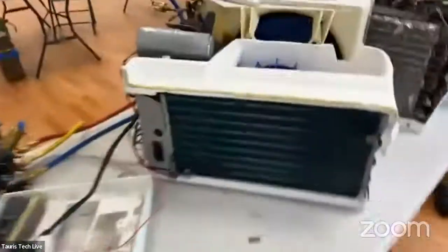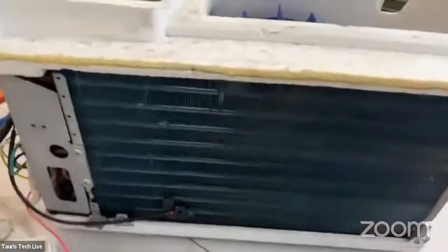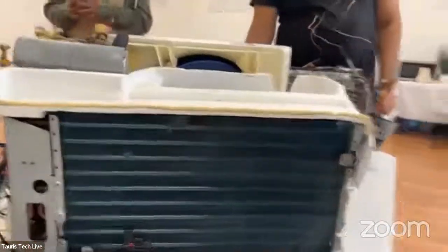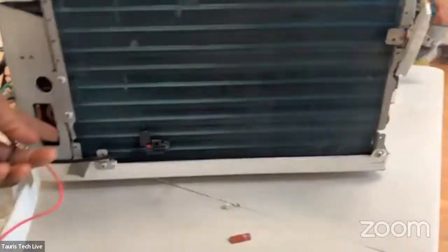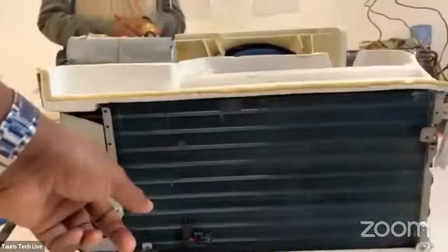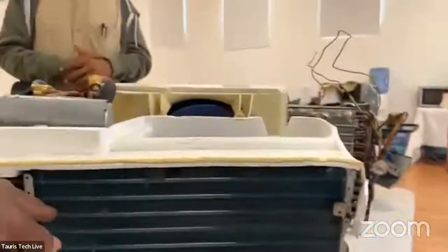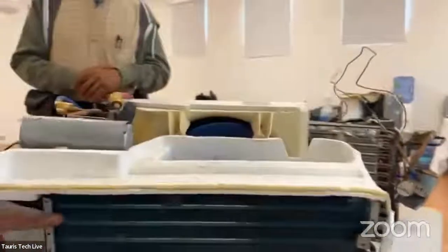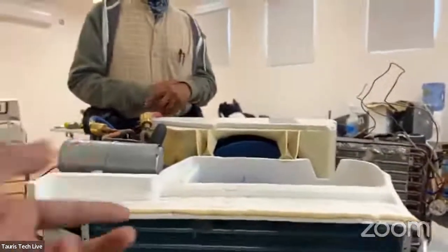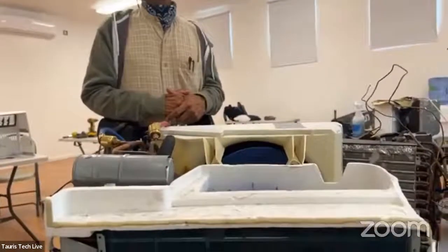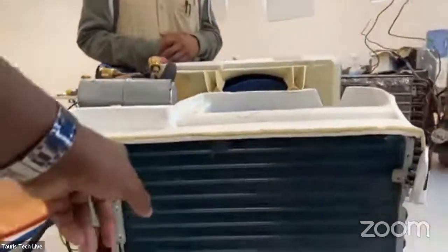Okay. So we have our evaporator coil here, right? If you imagine that our liquid refrigerant is entering down here and it's boiling as we go through the coil, and then at a certain point we have 100% vapor. Let's say the last 10% of the coil is being used for superheat. All superheat means is sensible heat. It means that I stop boiling.